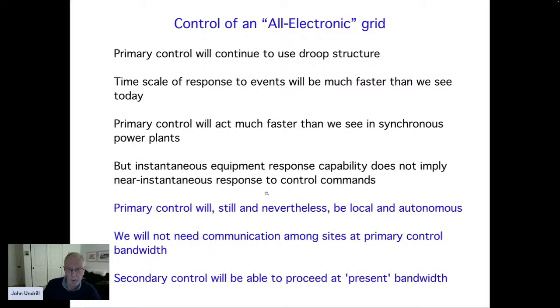I'm optimistic. I believe the present control protocols that we've been using and that we understand are going to be up to the task. The secondary control will, of course, be needed, and the secondary control will certainly be advancing over the next 10 years as our electric system evolves, as is everything else advancing. But it does not need to become preoccupied with getting ourselves down to very low latency and having a broadband with control. Secondary control can continue to operate on a much more economical use of bandwidth and the communication equipment.